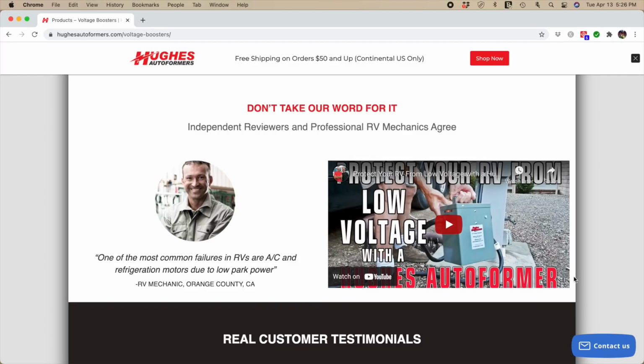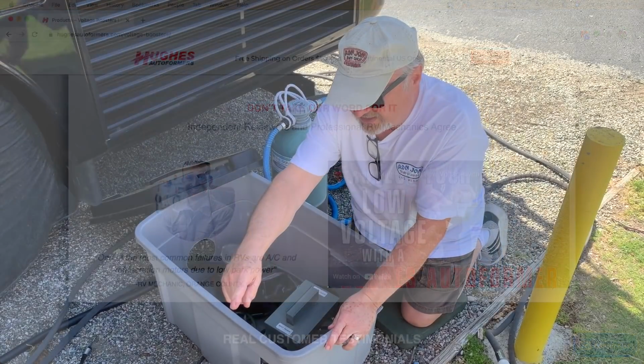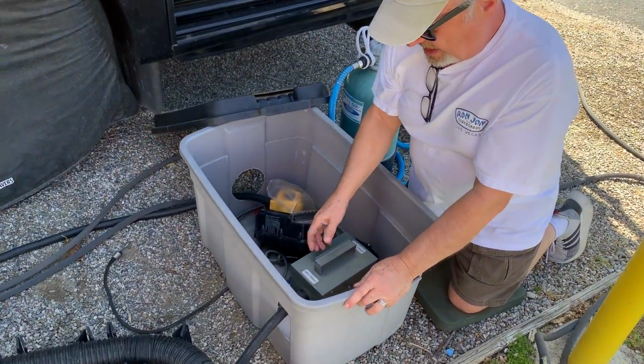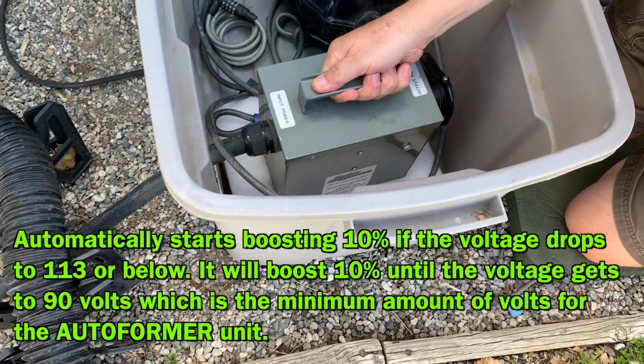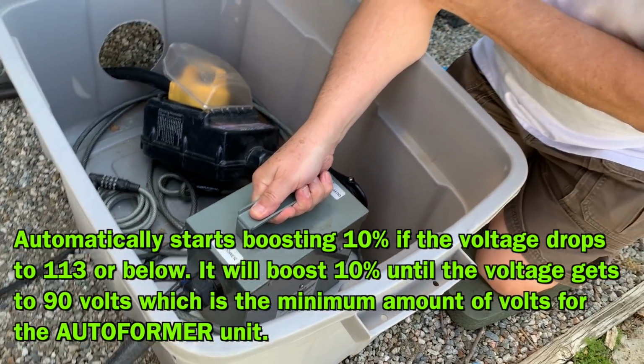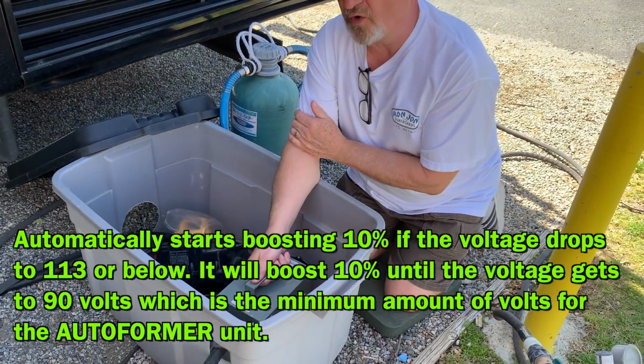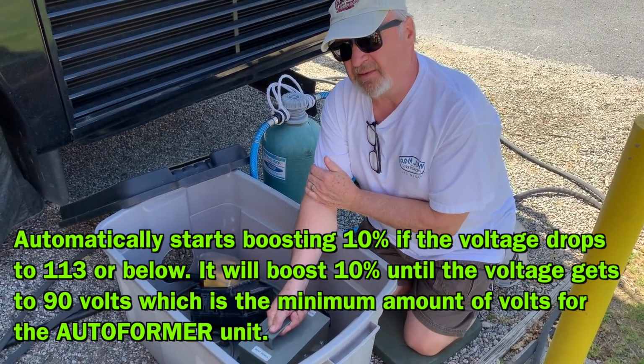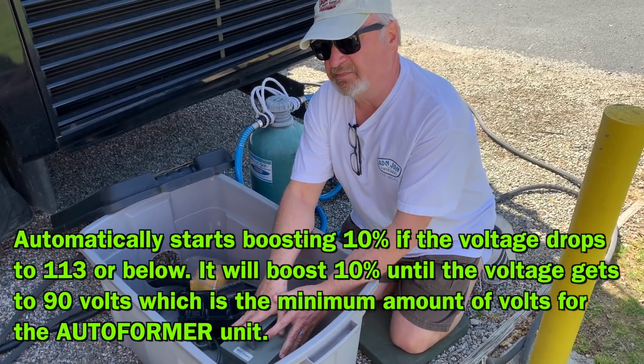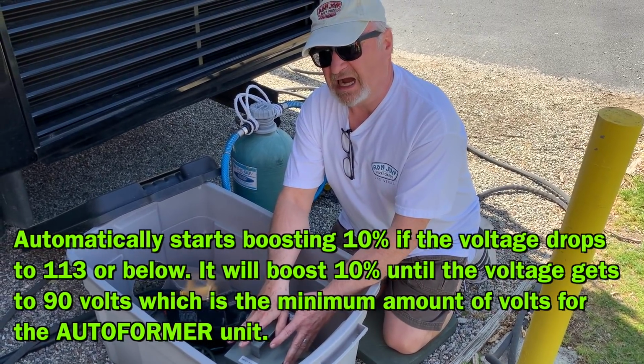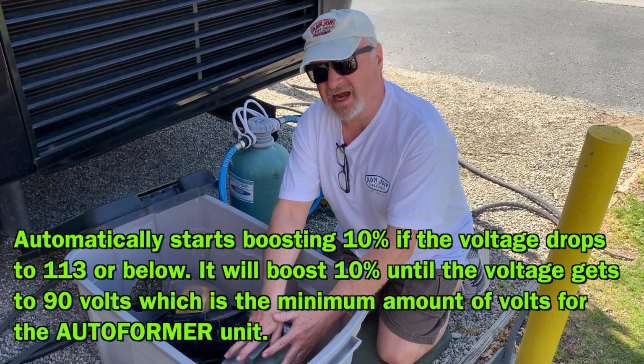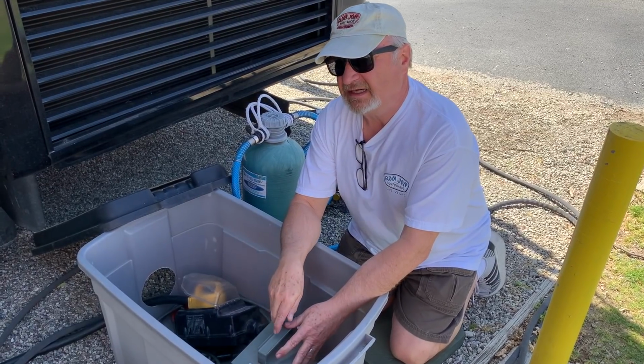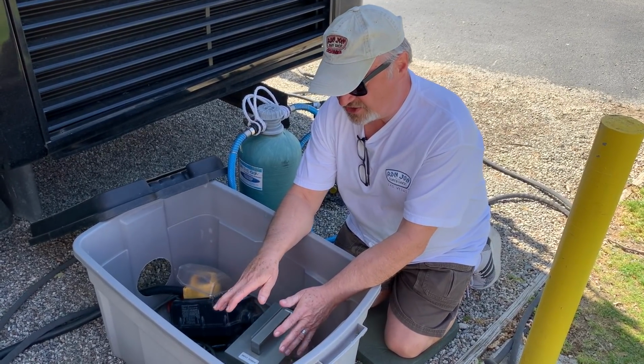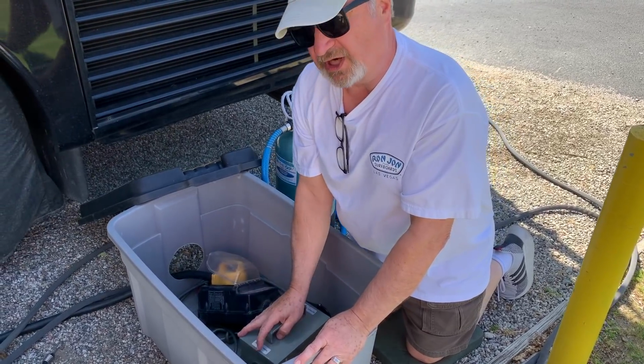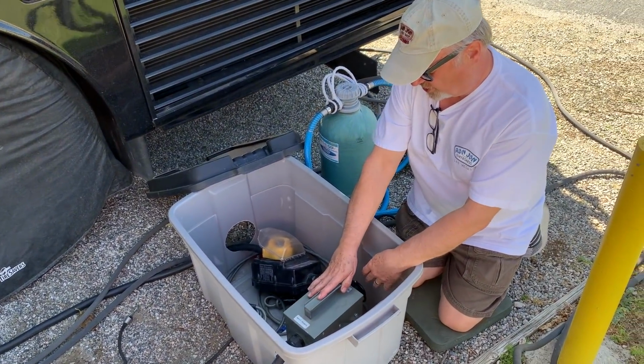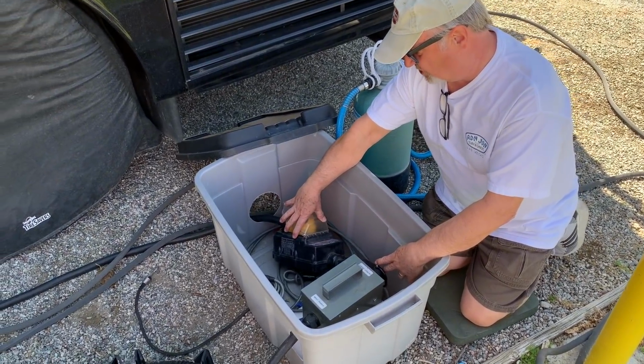We've had this since day one, so you're looking at one that's almost 4 years old. When the line comes in, the Autoformer's job is to boost your voltage if it gets below an unsafe value. If my memory is correct, I think it starts boosting at 112 volts. If that's not correct, I'll correct that in a text above. At a certain point, this unit will boost my voltage, which will then satisfy the next unit in line.